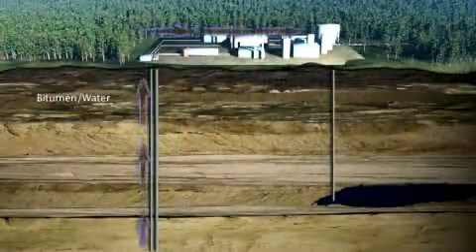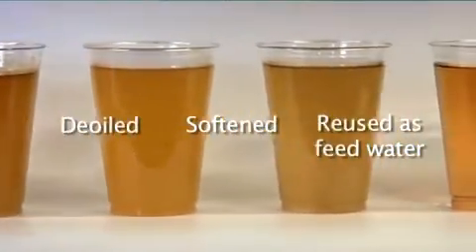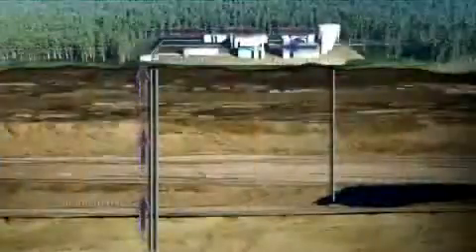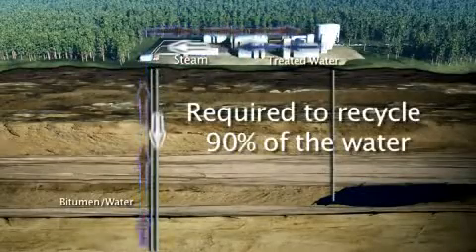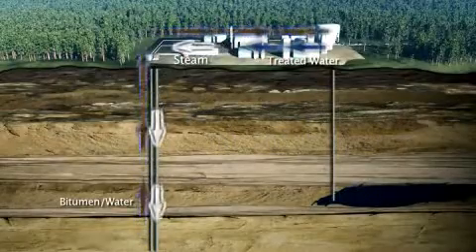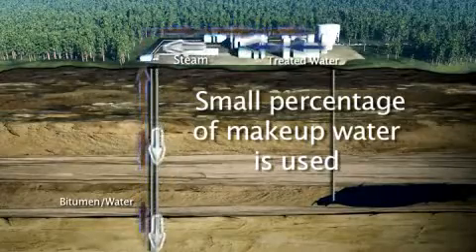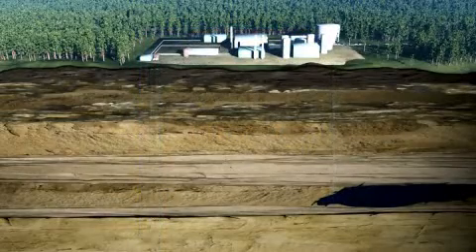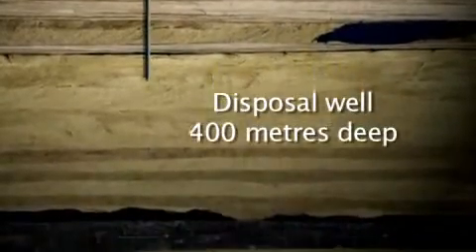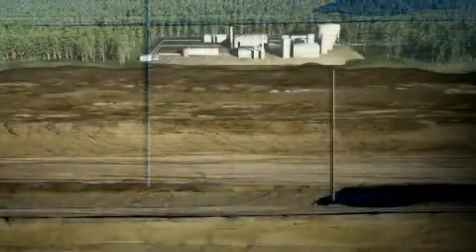The treated water is then reused as feed water for the steam generators. We are required by the regulator to recycle 90% of our water at Surmont Phase 1. To replenish the water retained in the reservoir and consumed as part of the oil sands operations, SAG-D operators need a supply of make-up water. The small percentage of water we can't recycle is disposed of deep into a well in the lower McMurray formation, over 400 meters below the surface. We then draw water from the aquifer to replace the water we've disposed of, and the process begins again.